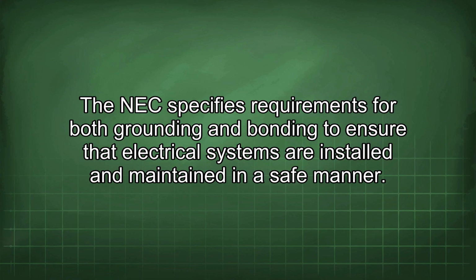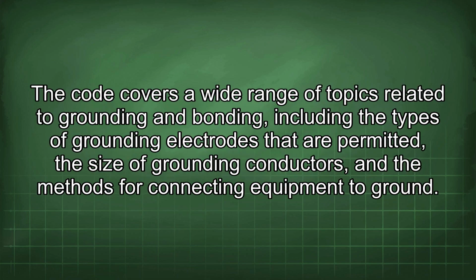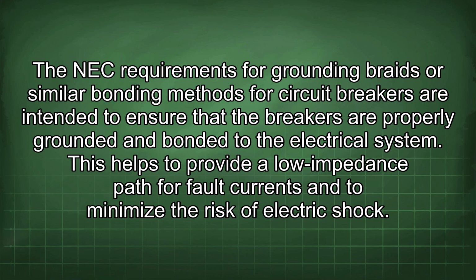The NEC specifies requirements for both grounding and bonding to ensure that electrical systems are installed and maintained in a safe manner. The code covers a wide range of topics related to grounding and bonding, including the types of grounding electrodes that are permitted, the size of grounding conductors, and the methods for connecting equipment to ground. The NEC requirements for grounding braids or similar bonding methods for circuit breakers are intended to ensure that the breakers are properly grounded and bonded to the electrical system. This helps to provide a low impedance path for fault currents and to minimize the risk of electric shock.